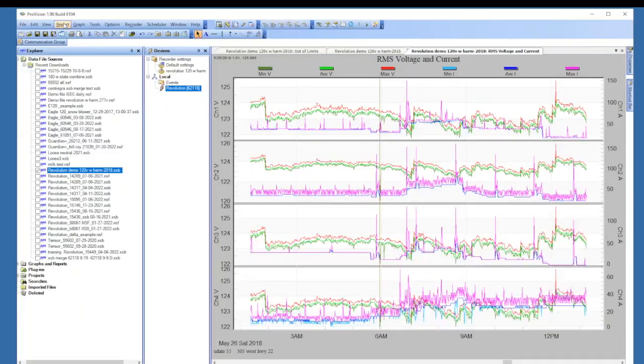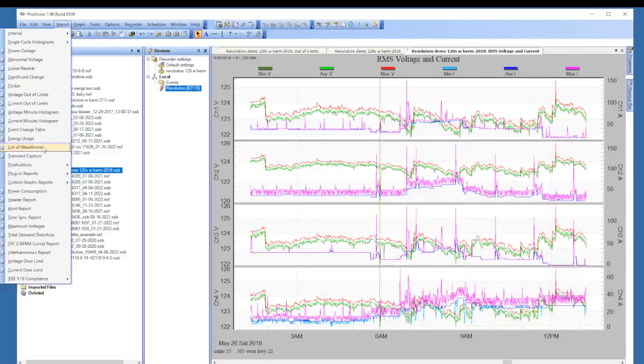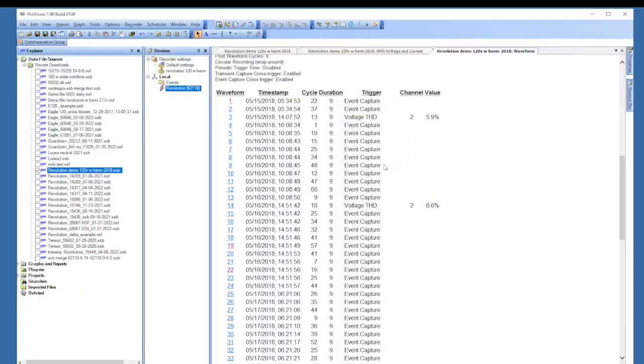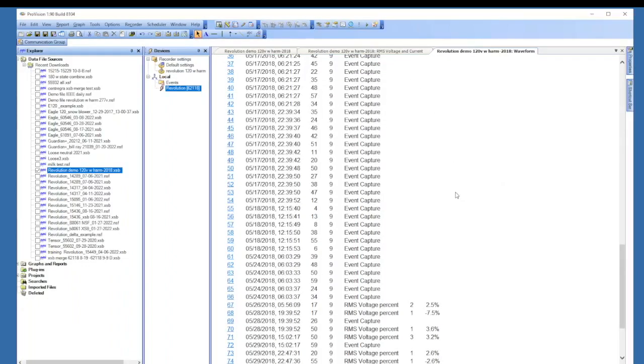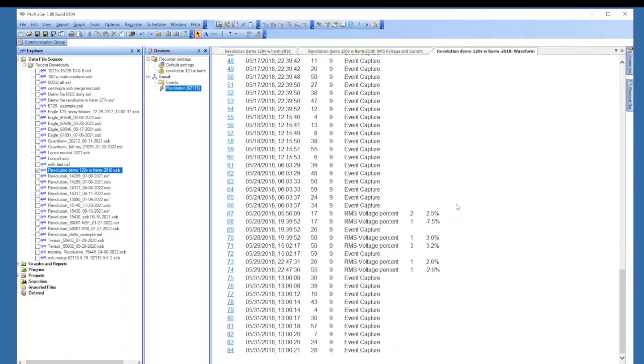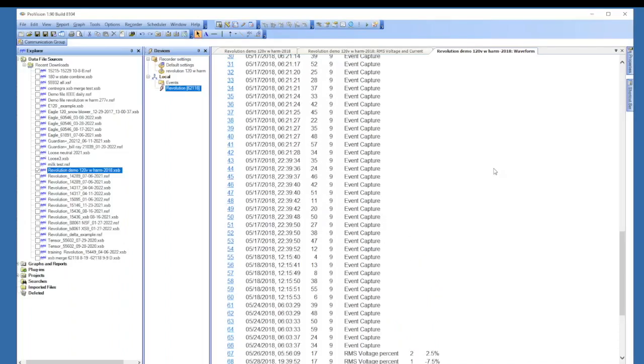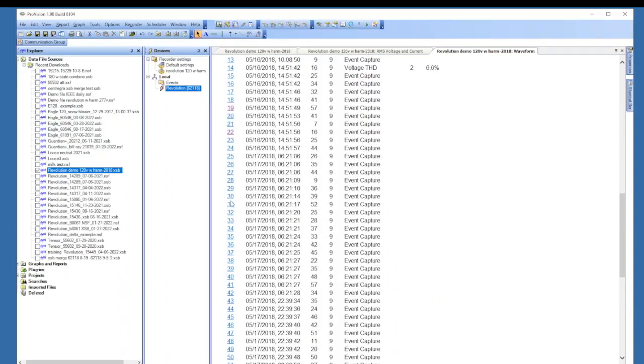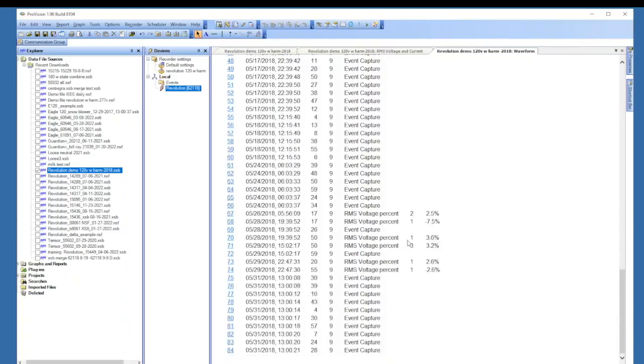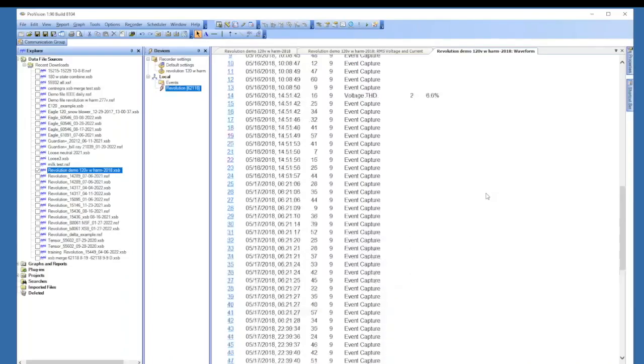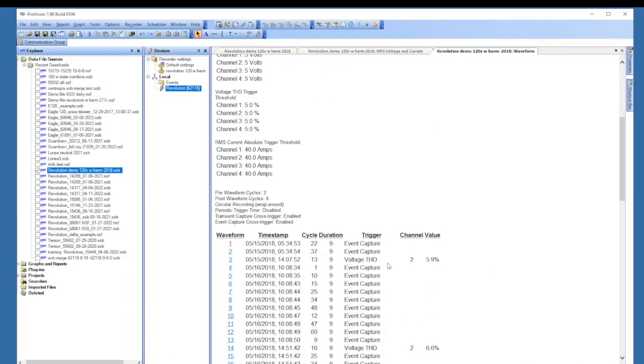that will take you to the waveform capture that occurred at that point. Now with the revolution, you can go into the report tab and there is a list of waveforms and it will tell you these were event captures. Like I said, that's kind of why I normally don't choose event captures. And remember, our event captures were configured for 126 and the voltage was pretty much over 126 that whole time. And you can just click on the number there to open up that capture. But see, a couple of these were from voltage percentages, and one was from THD. So the third one there is from THD.